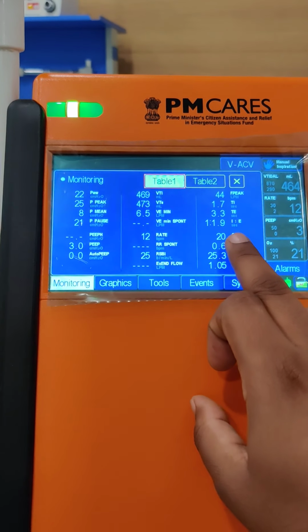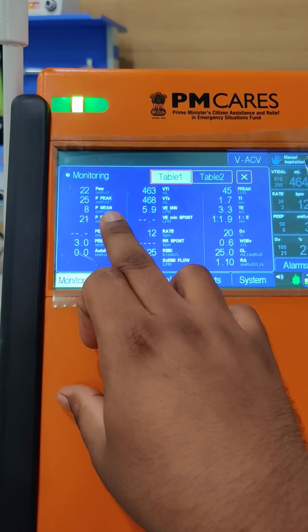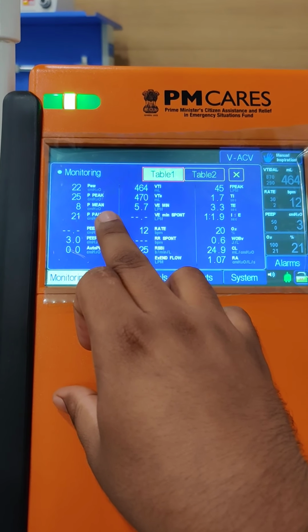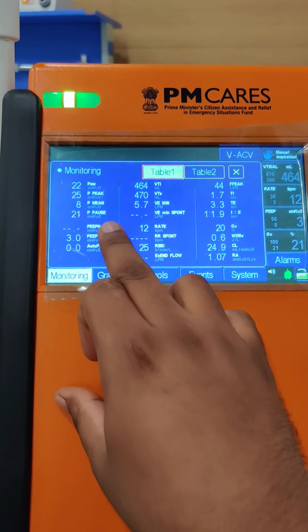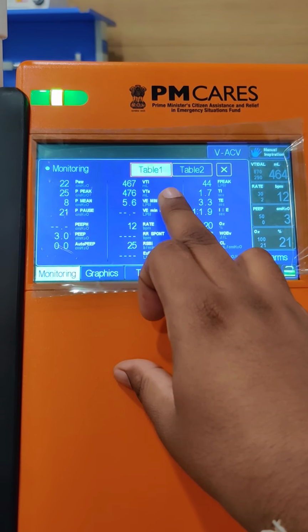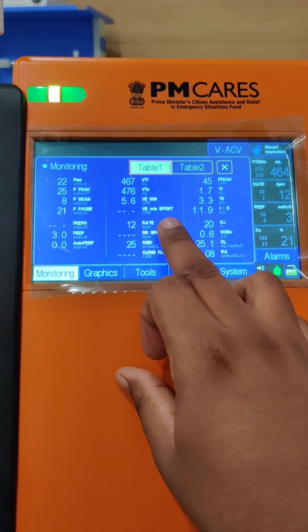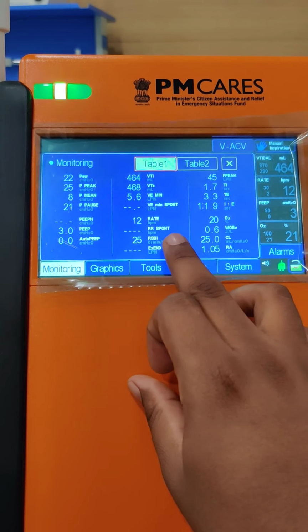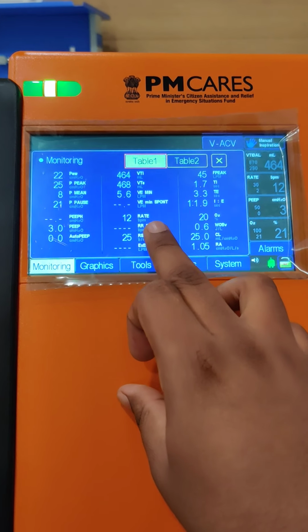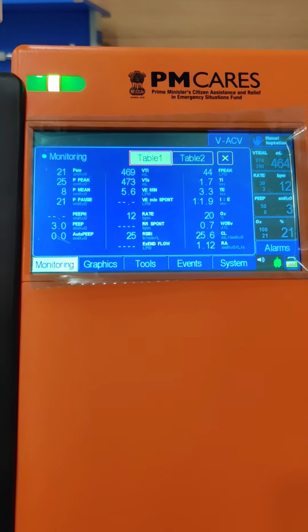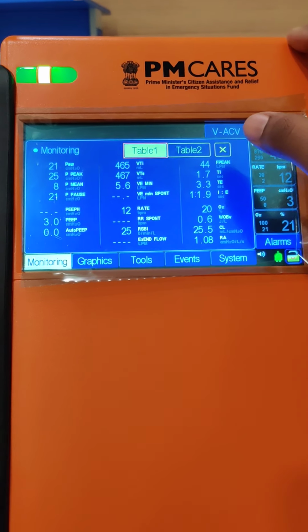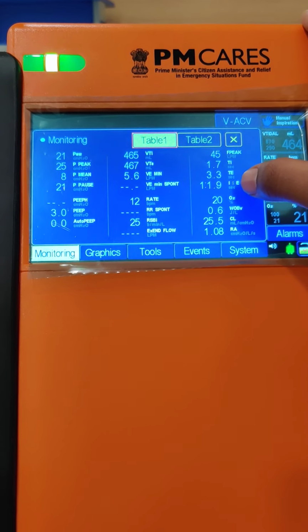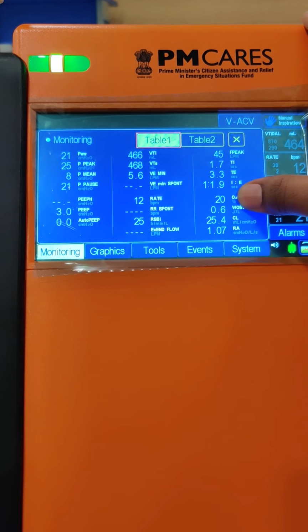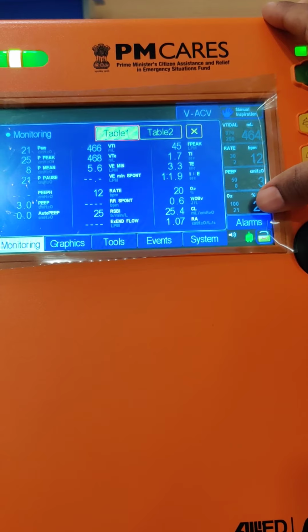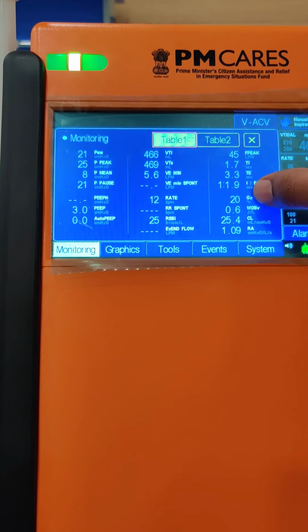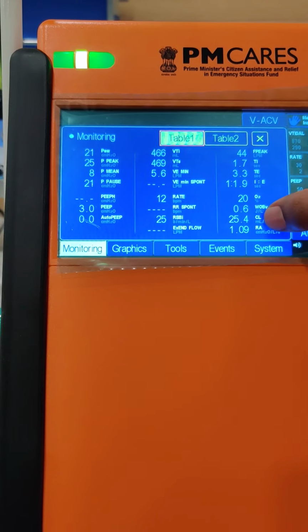So this is the FiO2, this is the airway pressure, the peak airway pressure, the mean airway pressure, and pause, that is the inspiratory hold time or the plateau pressure. This is the PEEP, inspiratory tidal volume, expiratory tidal volume, minute volume, frequency, the spontaneous frequency, the RSBI, and the expiratory end flow. Both the RSBI and the expiratory end flow are weaning parameters. Then we have peak flow, inspiratory time, expiratory time, and I/E ratio. Then we have the FiO2 delivered to the patient. If you set this at 40%, then O2 will be displayed as 40% on the screen. Then the work of breathing of the ventilator, the compliance and the resistance.